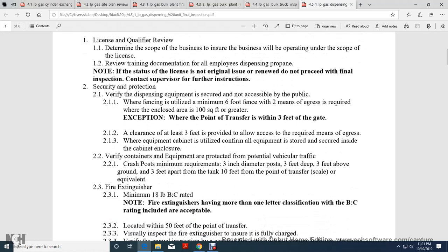Security Protection: Verify the dispensing equipment is not accessible to the public when fencing is utilized, with a minimum 6-foot fence and two means of egress. An enclosed area of 100 square feet or greater is required. Exception: where the point of transfer is within 3 feet of the gate, a clearance of at least 3 feet allows access. Equipment stored within a security cabinet enclosure also satisfies this requirement.